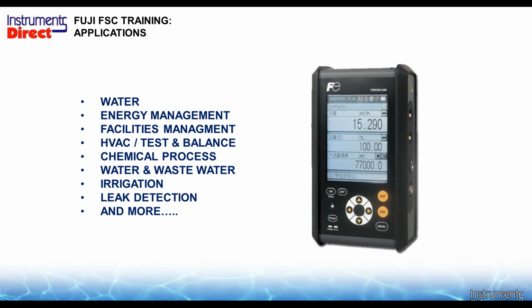So we use it on some wastewater, some sludge, and some slurry-like applications. The ultrasonic transit time flow meter is a completely different principle. Still some sound inside the pipe, but it uses transit time to calculate volumetric flow. So it works on ultra-pure liquid applications with no suspended solids, and it works up to about 2% suspended solids.